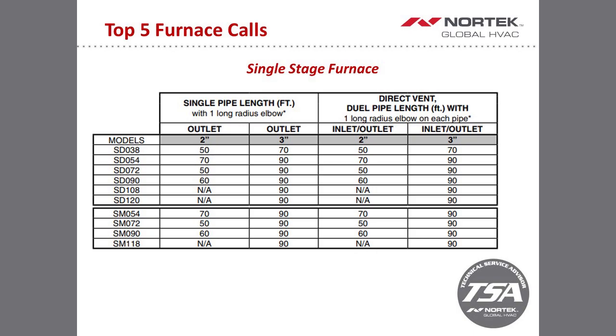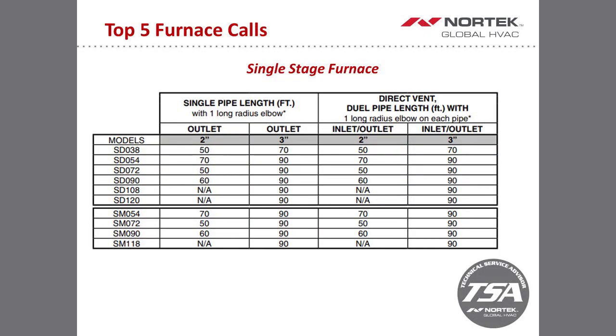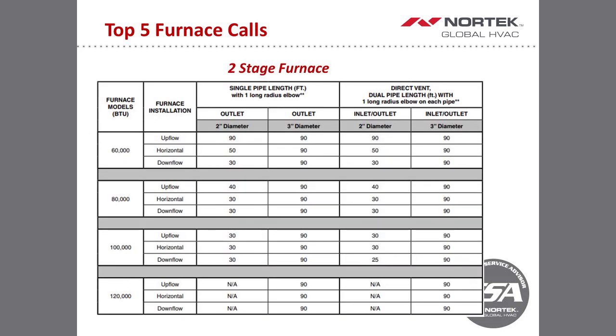If you go to a 3-inch pipe, there's nothing wrong with 2-inch pipe. What I just personally will suggest is that anything over 80,000 BTU, whether that's single stage or 2-stage, 80,000 or more, just go to a 3-inch pipe. This will cut down on nuisance pressure switch calls. Like I said, I'm not saying that 2-inch pipe is not approved or adequate for a proper installation, but sometimes through troubleshooting, when guys are using 5 or 6 90s in order to get piping outside, that stuff adds up pretty quickly on a vent table chart. So the numbers that you will have here in the single stage and also in the 2-stage table will include one long radius elbow, and then any elbow after that is going to be 5 feet. So like I said, if you've got four or 5 90s in a vent run, that's potentially 20 to 25 feet that you then have to add onto your linear length.